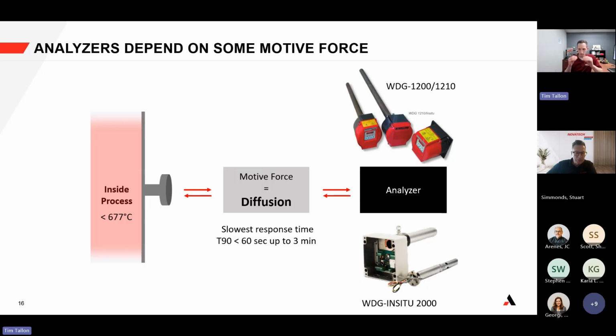In transport phenomena, the word for that would be diffusion. It's the diffusion migration from the process to the detector itself, make the measurement, and then the diffusion back out. And it certainly has a place in a lot of high particulate applications, especially difficult ones. The challenge is, though, diffusion's slow. I mean, Brownian motion is very slow. It's a very slow process. Even with a high velocity stack or high velocity firebox, it's still a challenge to ensure that that measurement is going to be made on time and within time.